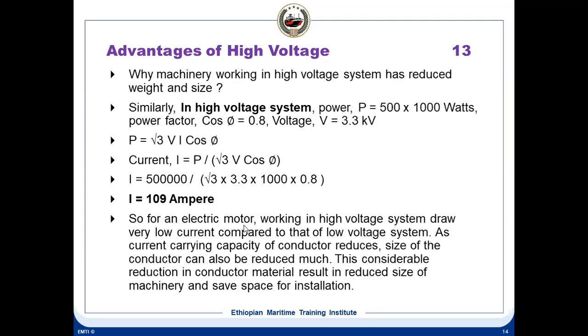So for an electric motor working in high voltage systems, drawing a very low current of 109 amps compared to low voltage systems, the current carrying capacity required of the conductor is reduced. The size of the conductor is reduced. This considerable reduction in the conductor size and material results in reduced size of the machinery and saves space for installations.